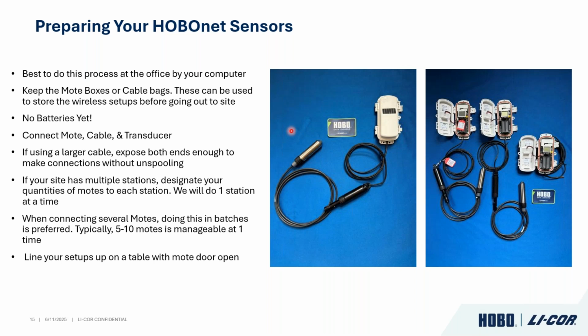At this point, we do not want to put batteries in yet. You'll see there's actually a toe tag right where the battery is, and it tells you not to put batteries in until all these items are connected: your cable, your direct read cable, your pressure transducer, and your mote. You want to connect all those first. If you put batteries in before they're connected, it won't recognize the sensor, won't give you the right readings, and will show an error.